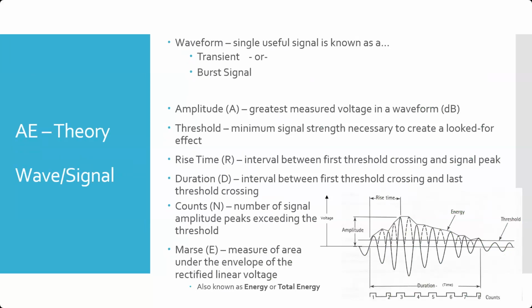The analysis that takes place is going to look at the waveform. We'll look at this a little bit bigger in a second. The amplitude is the highest point, where it peaks. So this here is a single auditory event. You can see there's a threshold, which is kind of the minimum. When the amplitude gets above a certain level, that's where we can say, yes, we're having an event, versus anything below the threshold, before or after this event, which would be your background noise, right? So you've got to establish what that background is. Rise time: how long does it take from when the signal first starts to break the threshold till it peaks? Duration: from when it starts to break that threshold until it stops breaking the threshold. Here's the duration at the end.